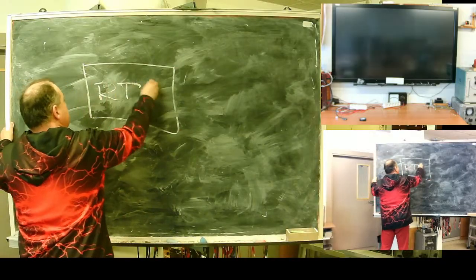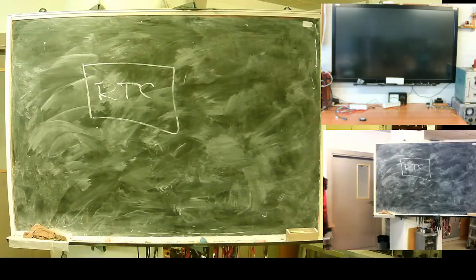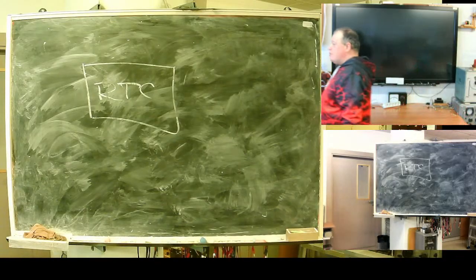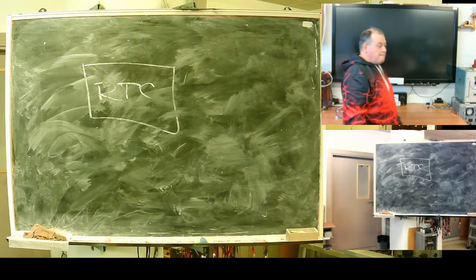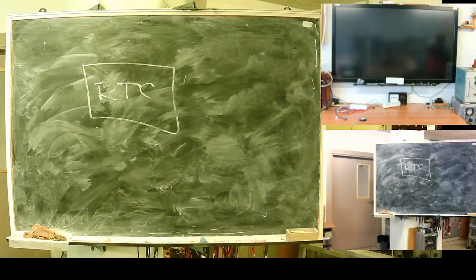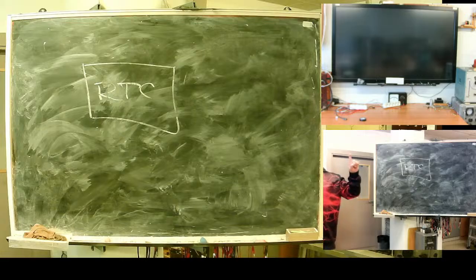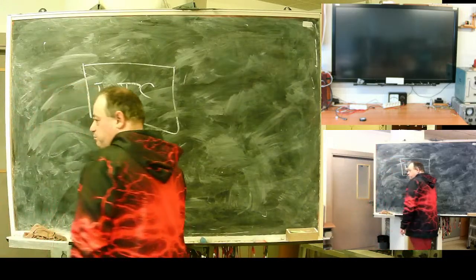A nice thing like RTC, real-time clock, should be redundant and have battery backup. A simple device has just a clock, but more complex devices, whose interoperability depends on device-to-device measurement comparison, should have a precise real-time clock, because they operate with time-stamped values, and an error in timing may ruin things. For example, when you compare currents on two ends of a line, a shift in time means an error in comparison. So the clock is an important thing.